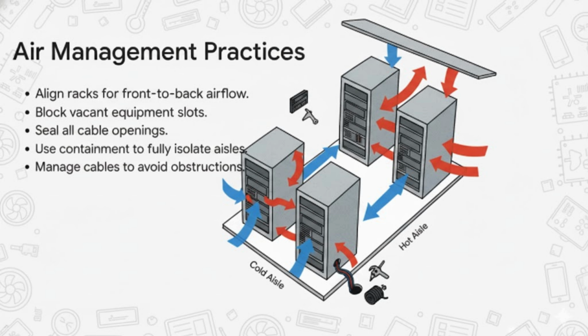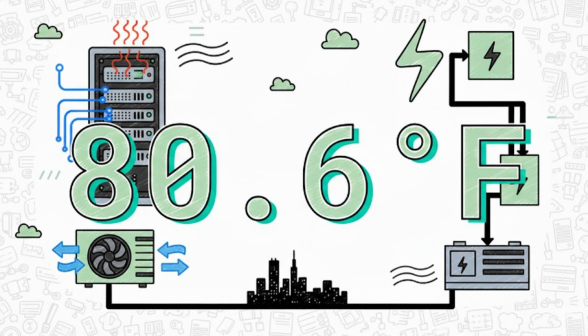Every detail matters. Here's a number that surprises almost everyone. We all have this image of data centers as these meat lockers, super chilly, like 65 degrees. Well, not anymore. Modern gear is built to run way warmer. The recommended upper limit from ASHRAE is actually 80.6 degrees Fahrenheit, that's 27 Celsius. Letting the data center run warmer like that dramatically slashes the energy you need for cooling. Every single degree you can raise the temperature saves a ton of money.